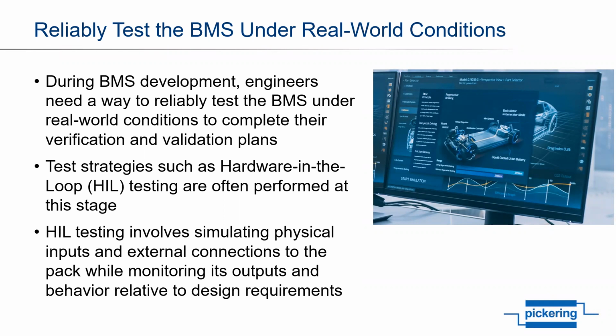This is where hardware-in-the-loop testing comes into play. Hardware-in-the-loop systems are used to simulate physical inputs as well as external connections - in this case, the battery stack and BMS. To the BMS under test, these simulated inputs appear as real-world signals would, meaning that you can test the behavior of the system under test in a much more controlled and repeatable environment.